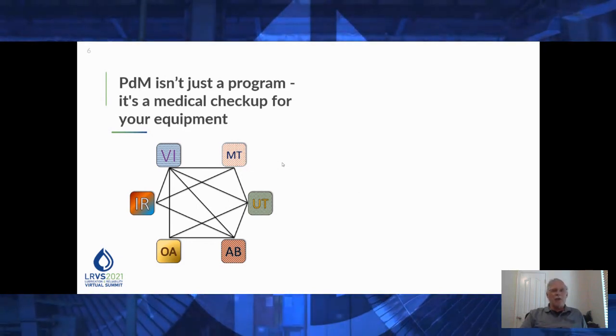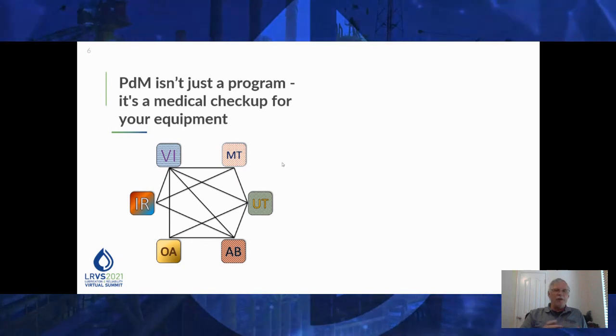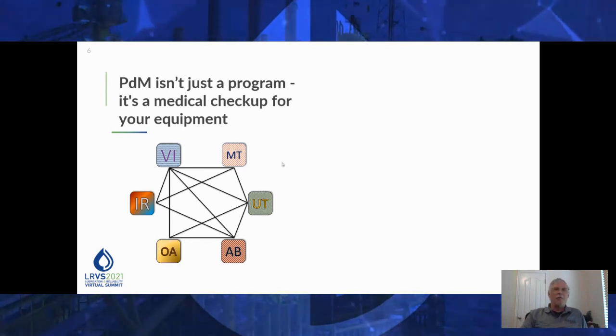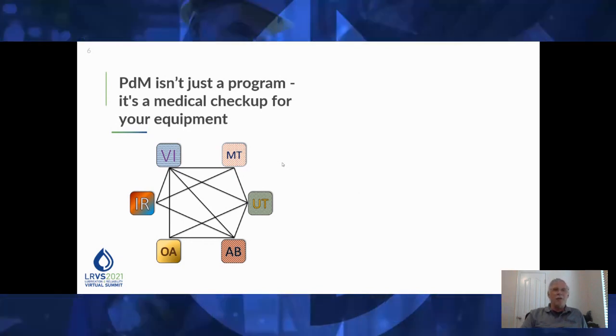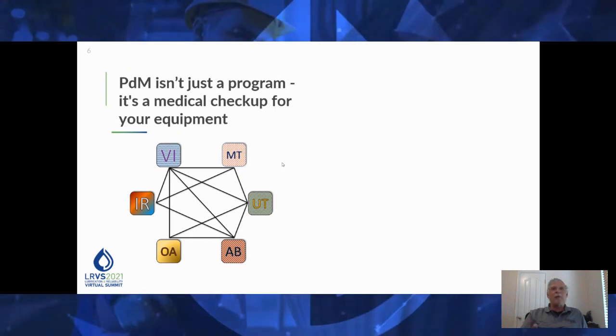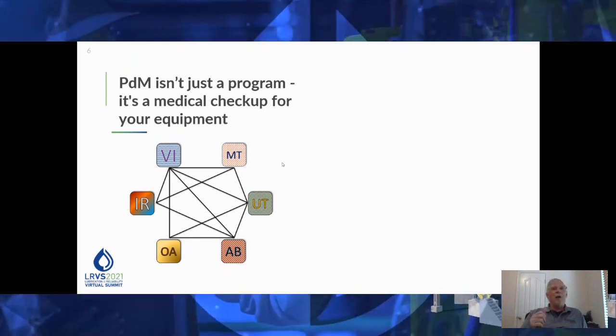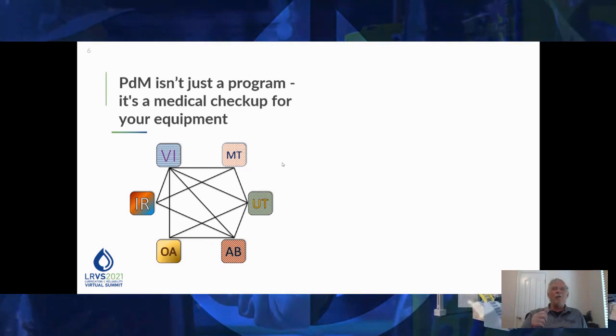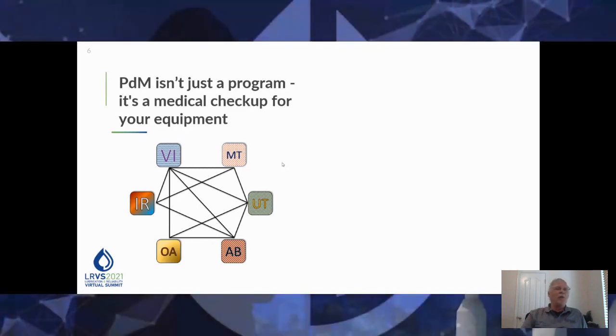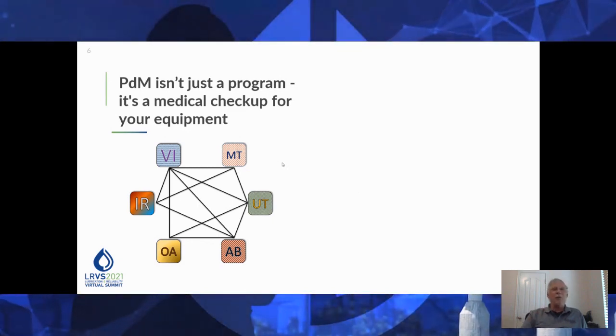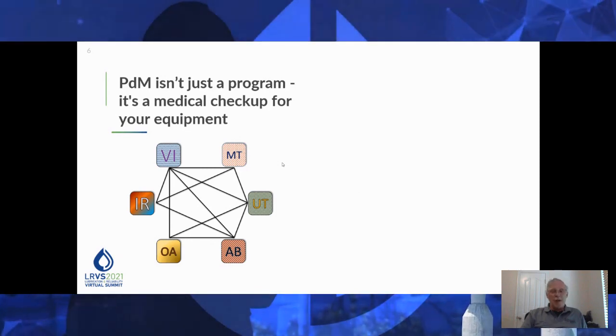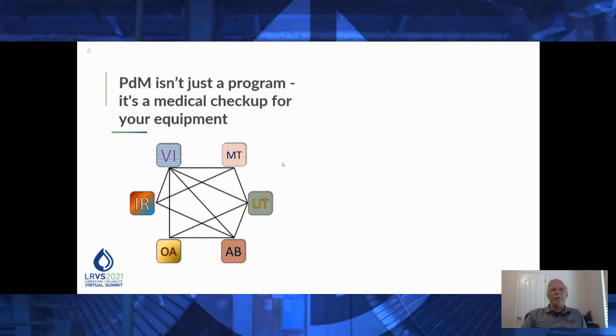If you've got a coupling that is visibly hot in your infrared survey, then you've obviously got something going on. But if you have no vibration and no motor issues, and you know you did a good alignment, then probably the problem is just the coupling.